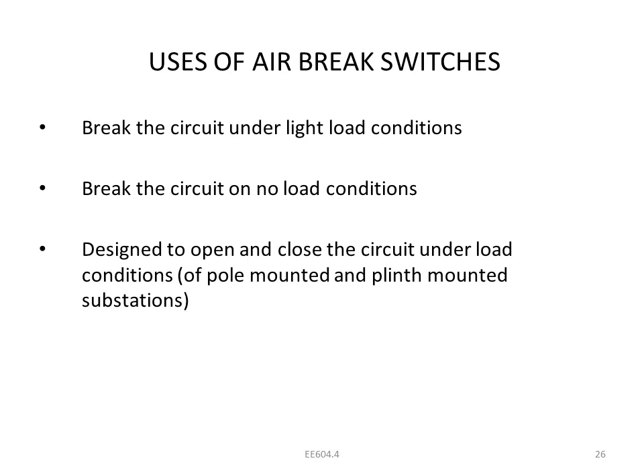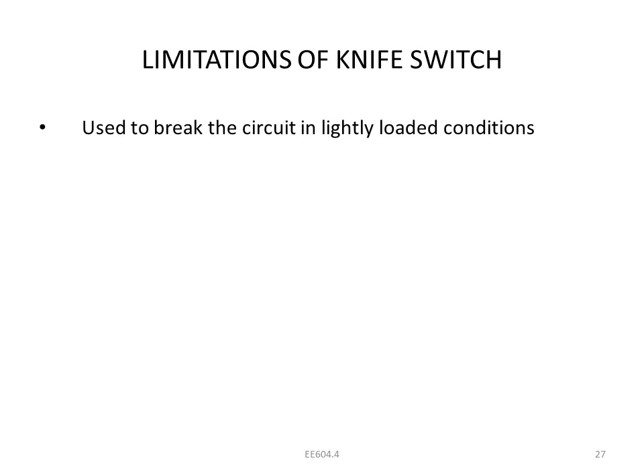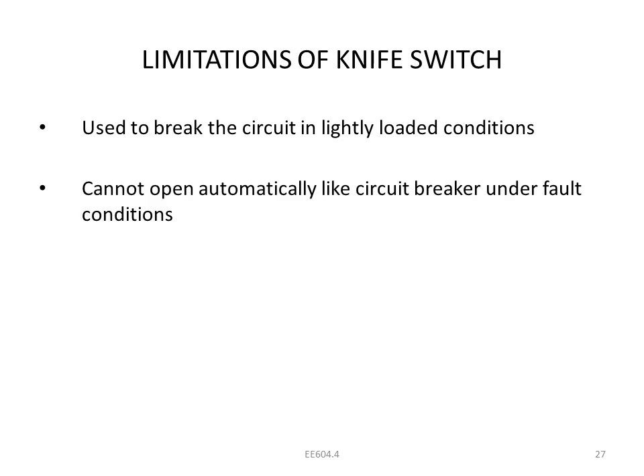So, possibilities and limitations: the air break or knife switches are used to break the circuit under light load conditions and cannot open automatically like a circuit breaker under fault. So this is like a switch. It will not work as a switch to make and break the circuit under fault. You should be careful while operating under load condition, as it can be damaged if fault conditions continuously occur, and that will cause further huge damage.